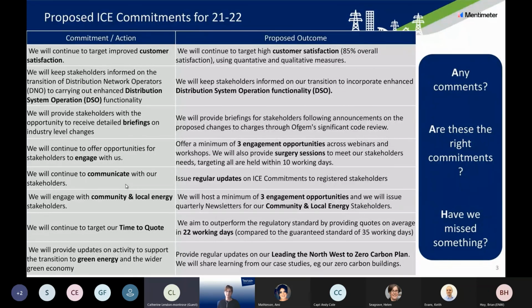We're finding now that we're ending up dealing with a lot of the homeowners who are applying for the Smart Export Guarantee. And they are now being driven by the utility companies to get more and more information to allow them to set up their export guarantees. That's not something that we've seen necessarily from the DNOs in the past, with confirmation or acknowledgement of acceptance on a plot by plot basis when we submit commissioning documents for G98s. I don't know if that's something that's planning to change as part of your process. It's much more of an admin query compared to some of your big commitments, but it's something that will make a big difference to the work that we have to do.